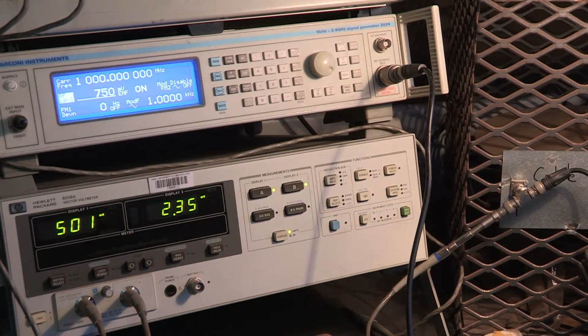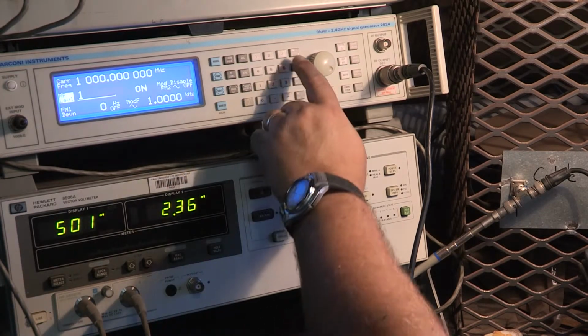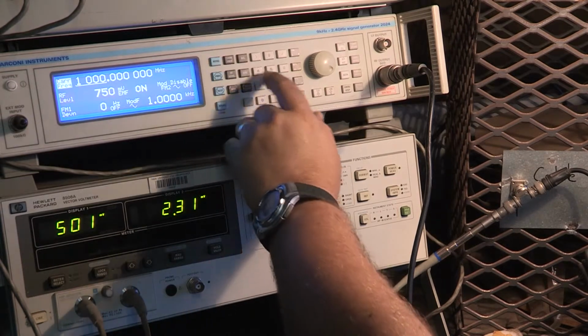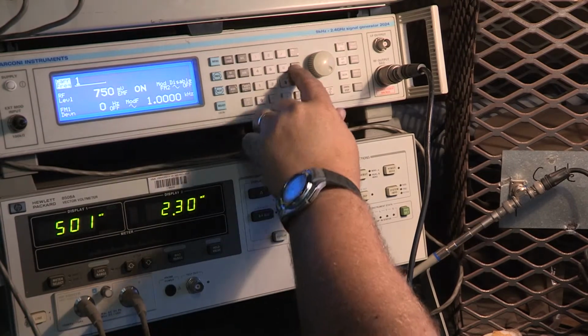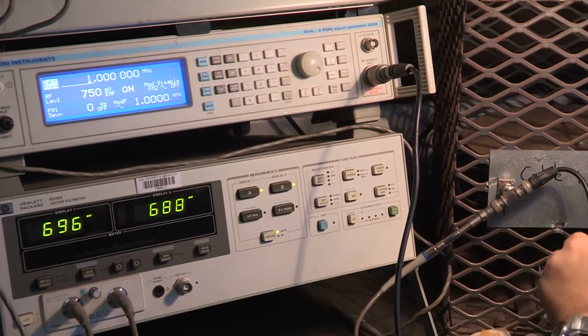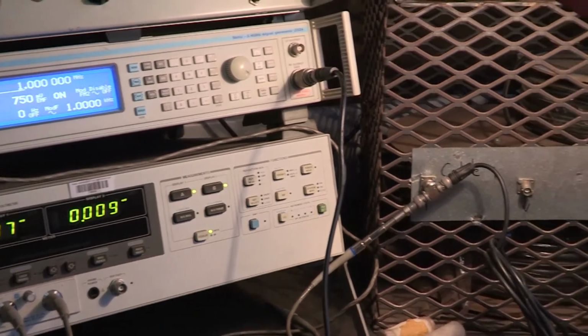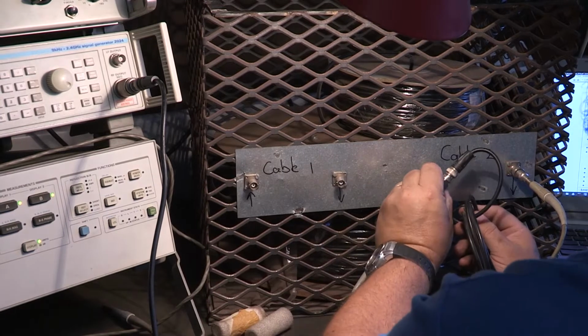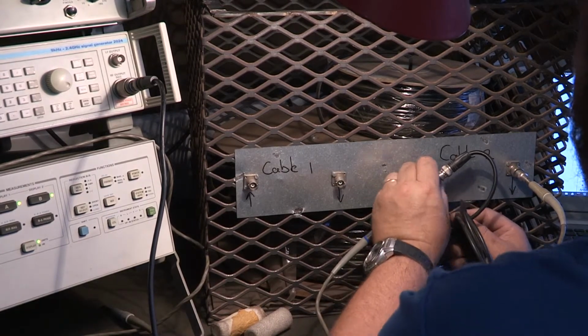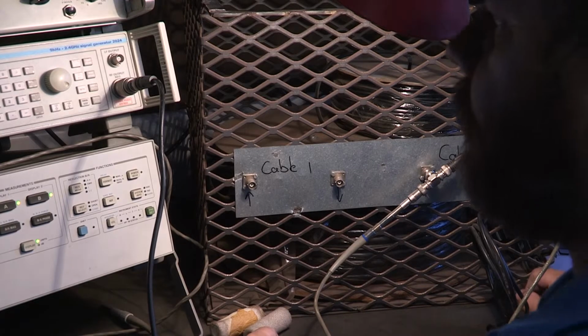By doing this, now the cable is actually slightly improved, can you believe it? So it seems to be liking microwave frequencies. That's cable 1. Now we're going to start all over. Let's go there, and then go there, and over there, 1 megahertz. But now, instead of cable 1, we're going to measure the second cable. We want to compare the two cables. Hence, the same readings, the same frequency steps, but we are expecting different readings.